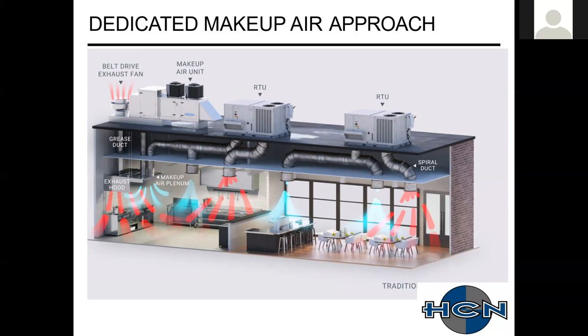So typical design, your dedicated makeup air unit would be doing about 80%. You have about 20% coming from transfer air between the two rooftop units. And as long as everything's working properly, you typically don't get any calls. Usually what happens for most systems that I run into that have problems is it's a makeup air problem. The makeup air unit was undersized. The rooftop units may have been undersized and were pulling too much transfer air. The exhaust hood itself is not pulling the proper amount of exhaust air. The returns in the space are interfering with each other. There's a lot of things that can go wrong in a commercial kitchen hood system.